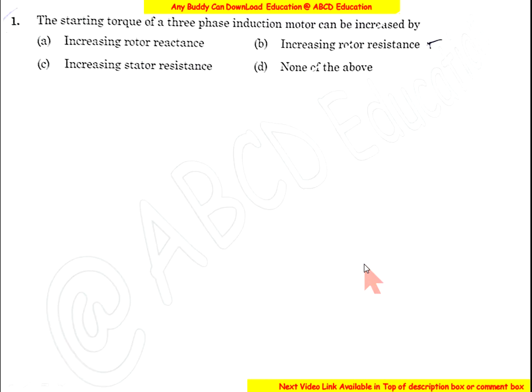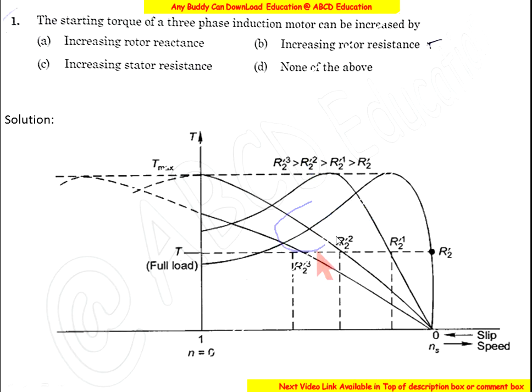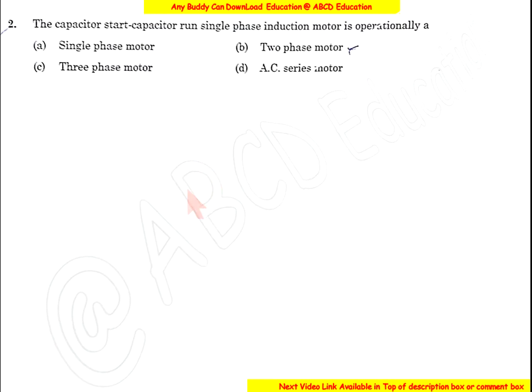Question 1: The starting torque of a three-phase induction motor can be increased by increasing rotor resistance. From the torque-speed characteristics, if resistance R2 is increased from R2 to R2_1, the starting torque increases. Increasing further from R2_1 to R2_2 increases the starting torque further. So the correct option is B: rotor resistance.